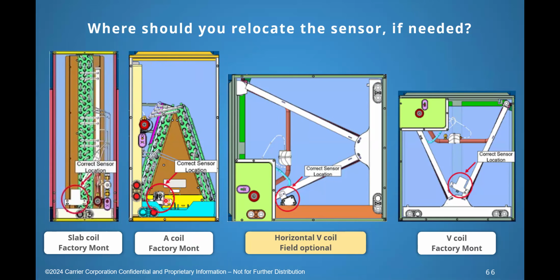It'll pool low. So in this case, if you take this whole thing and turn it on its side, that's fine because this is still the bottom corner. It's a different corner, but it's still the bottom and it's okay. If you have a V coil, it's also fine. It goes in the bottom of the V coil. Life is good. But if you get a V coil multi-poise, meaning a drain pan here and a drain pan here, and you mount it on its side, what used to be the bottom now becomes the middle, and it's in the wrong spot. So you have to take 2 screws out, slide it down over here, and put the 2 screws back into the screw holes that are already there. And now your leak sensor is at the bottom again. So there's one time that they have to relocate it: on a multi-poise V coil for a furnace. That should be the only time.